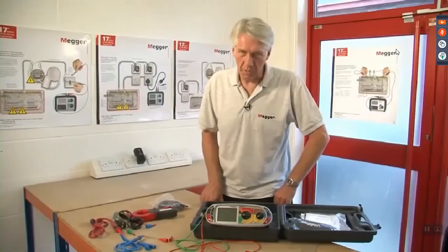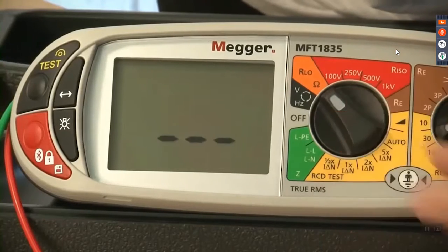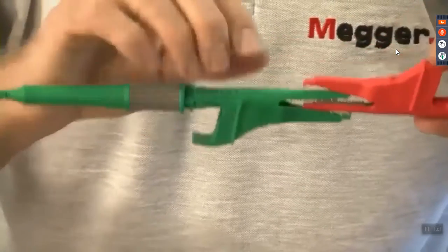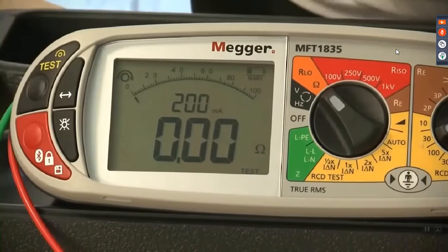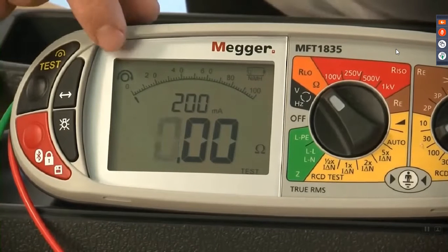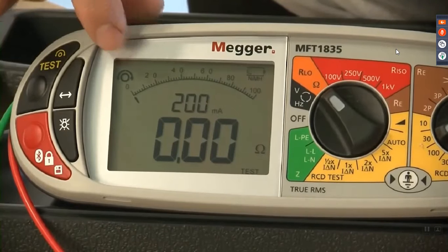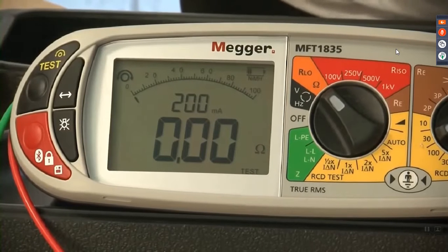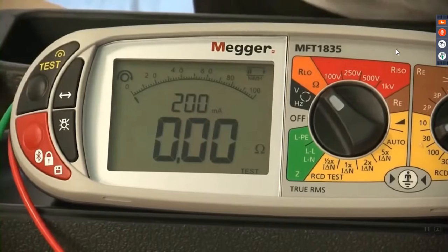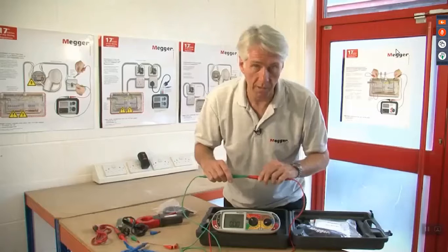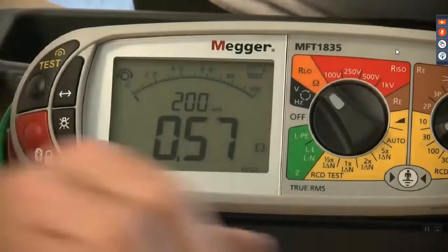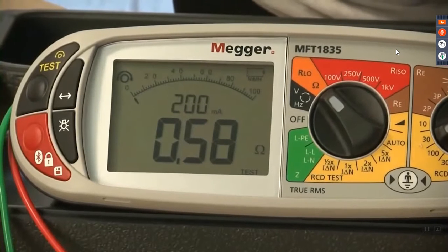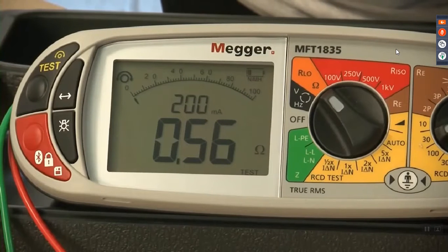Next we'll do continuity measurement. So we select our continuity range. The next thing we have to do is null out our lead set using the non-hinged part of the clip. Once we've got a stable reading, we press the test button and the indication shows that lead null is now in place. If you wanted to simply check continuity on a cable, you can turn the buzzer on and off again just by pressing the button. What we'll do now is apply a known value of resistance. So the buzzer is turned off, and we get a reading here of 0.56 of an ohm.